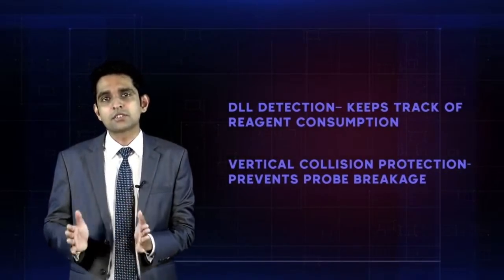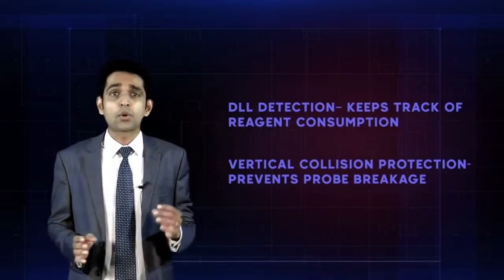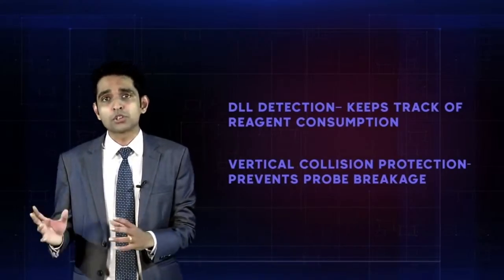CXL Pro comes with a polished probe which eliminates any kind of carryover and increases the accuracy of the result. The product also comes with 2-level washing for the probe: an internal wash which is a pressure wash, and an external wash which is a waterfall wash.